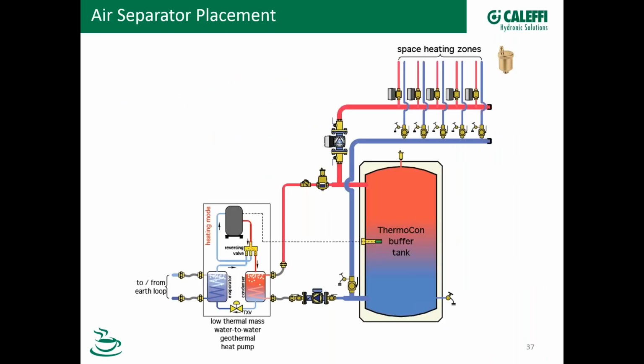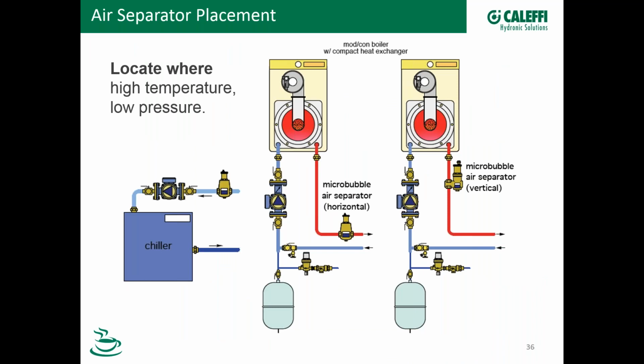Hey, Kevin. Yes. Going back up to that last one, a question came in. Is the air separator placed directly after a boiler always the best location? And as you show it here, directly after the boiler. In many cases that's true, but we have to remember the pressure effect on air coming out of solution. Let's say, for example, our zones are 2 or 3 stories up before we start branching off. Now, as that water has traveled up, albeit at pretty much the same temperature as coming off the boiler, that reduced pressure as you go up the building is going to release more air that you otherwise wouldn't have captured with the separator placed exactly there.